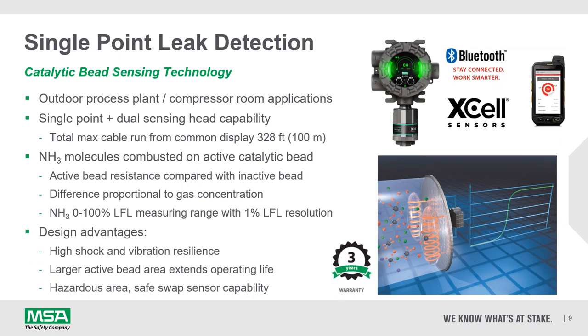Bead design can affect its performance, and larger and more robust designed elements make it suitable for areas where there is shock or vibration and can extend the life by having a larger surface area. When needing to replace the sensing element, again a safe swap capability is available, meaning you don't have to declassify a hazardous area before doing so.